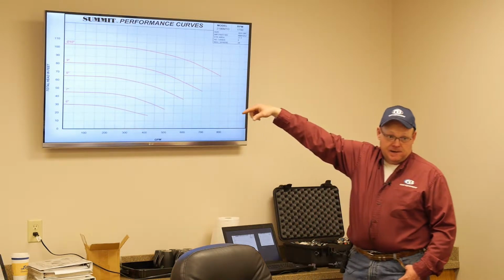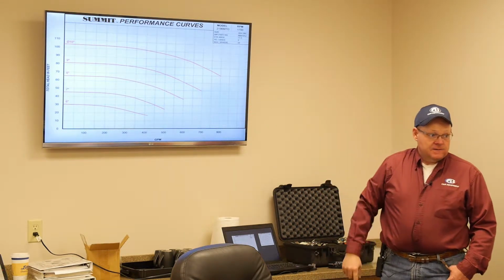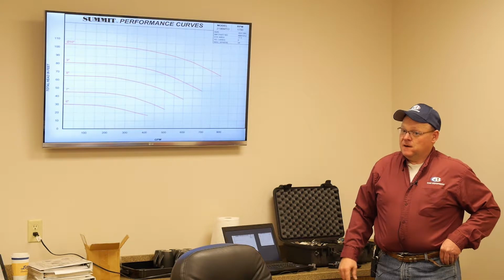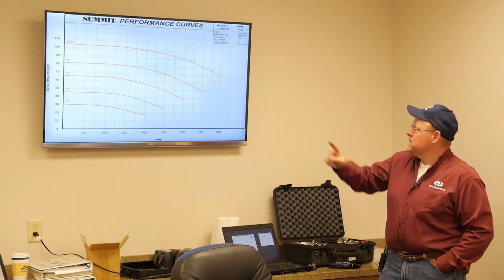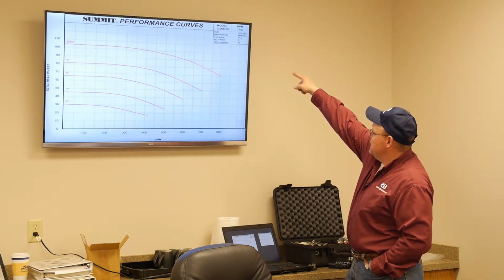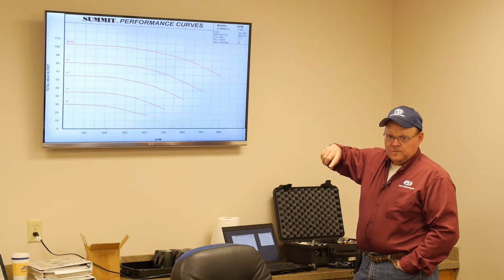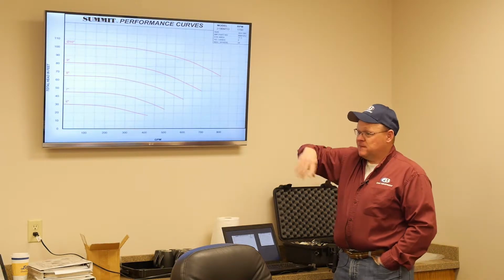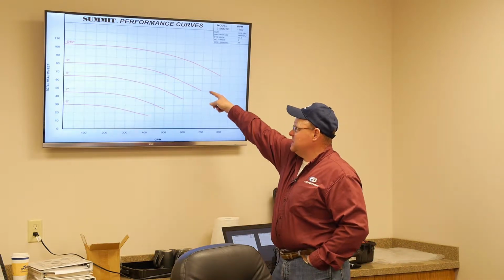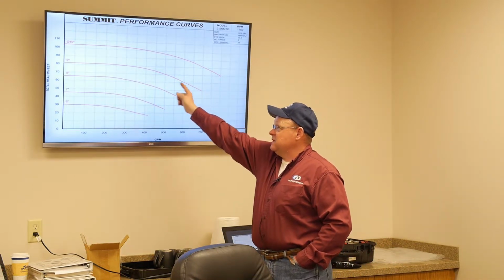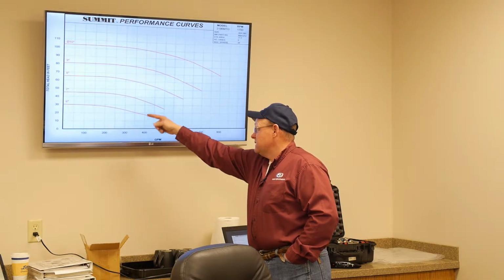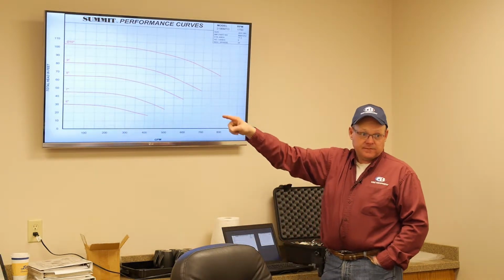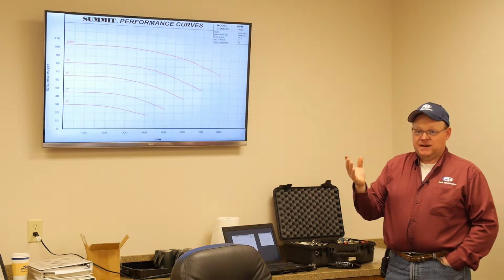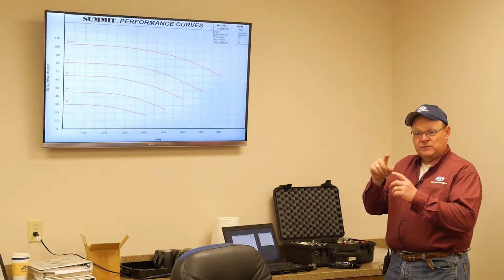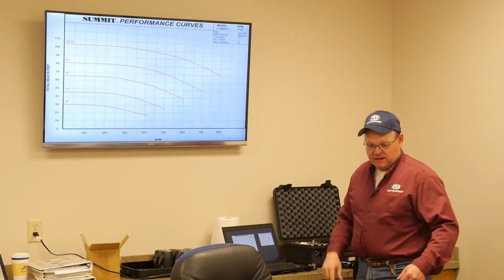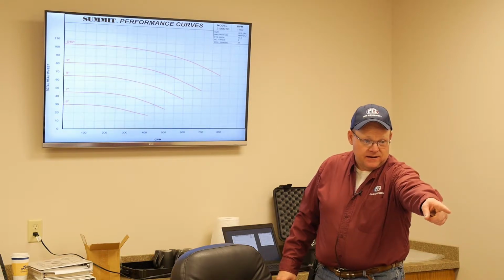What are these other lines on here? Different impellers. Different size pump. Nope, same pump. If you look up here in the right-hand corner, 3410, same pump. Same head. All we did was we have a 10-inch impeller. We went out there to the lathe and we trimmed it to 9, 8, 7, and 6. So we just trimmed the impeller, but you see how we're taking that little bit off the exterior of it. That's a 10-inch wheel right there.